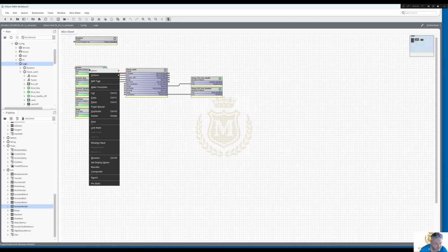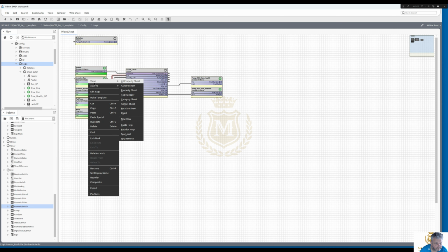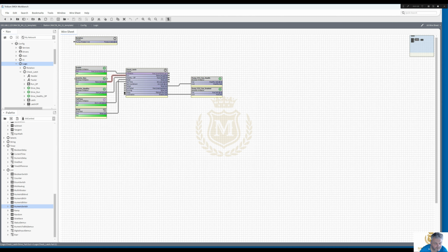We enable the inverter or the pump. Now it's still saying manual run because it's expecting a feed from the inverter to say, hey, we're running, or the DP. So let's just activate that. Now we've got the enable, everything's healthy, and there's no fail time, there's no fail countdown there, everything is healthy. So not failed, true, and we're running. We've got the run signal there.